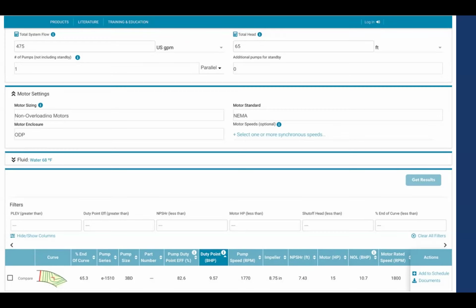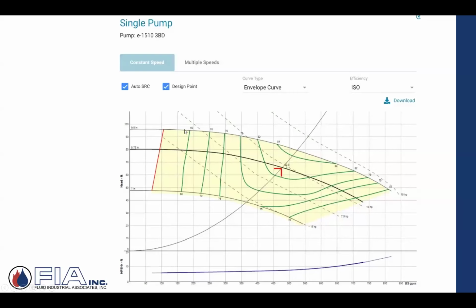And now I've protected myself. Regardless of operation of that system, I'm not going to overload, because that impeller performance curve never goes past, never gets close to that 15 horsepower. It's a safe selection. It's always going to be fine. It's never going to overload in this example.